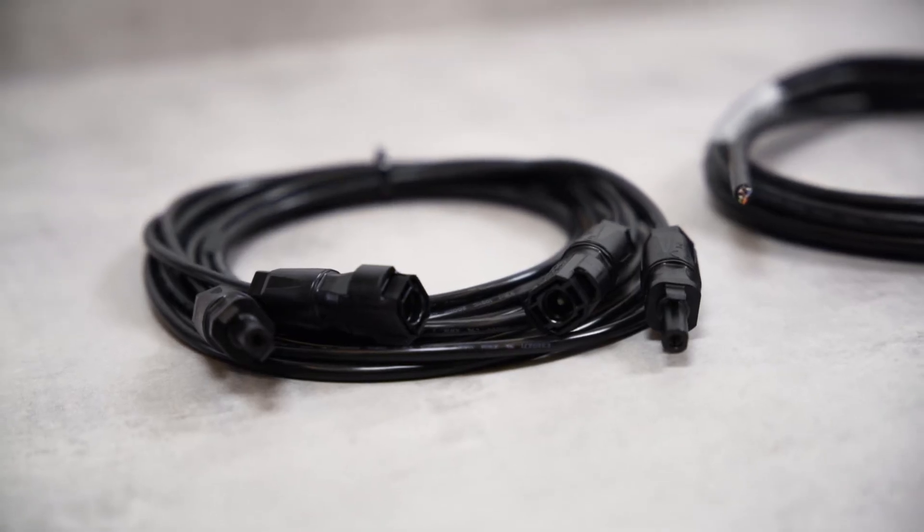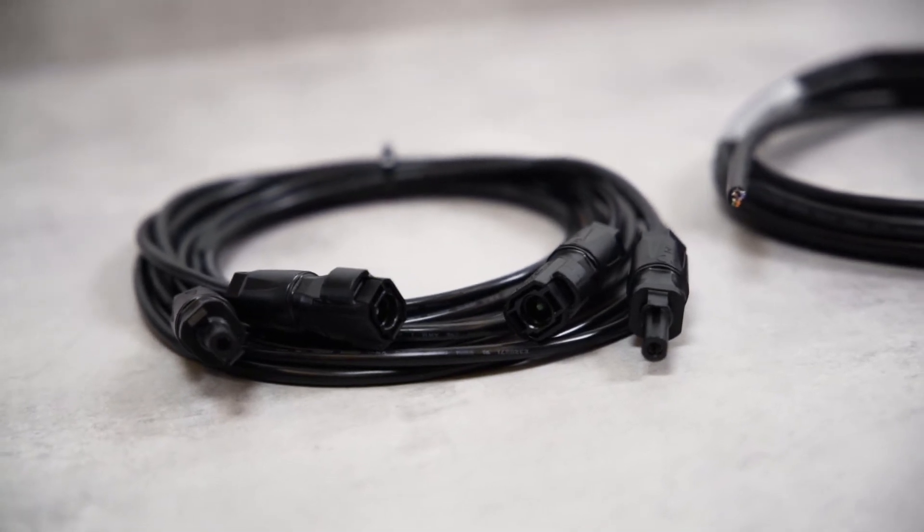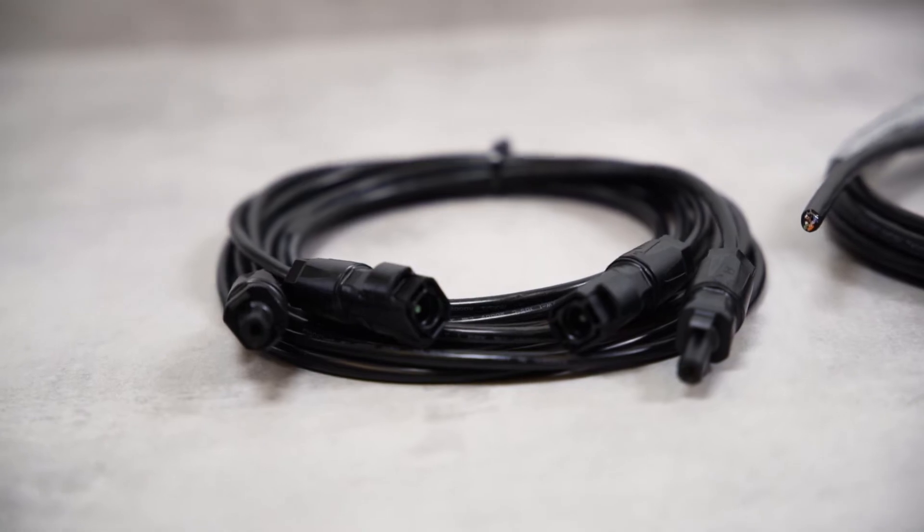Before the inverter can be connected, the AC home circuit breaker must be disconnected, the cables must be de-energized and in perfect condition. Before installation, make sure by measuring that the cables are really voltage-free. You will find all cable requirements and wire sizes in our manual.